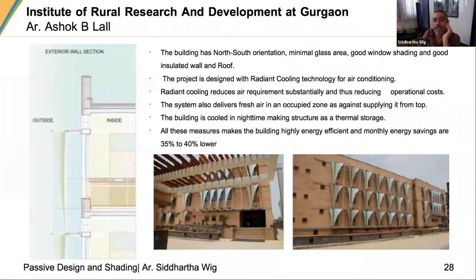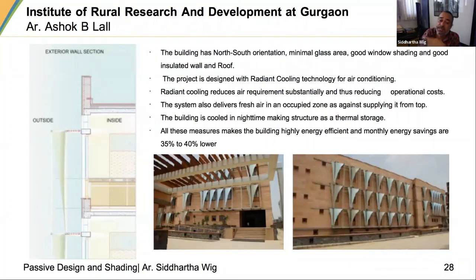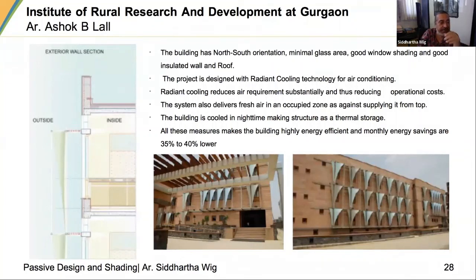The building uses its orientation well and windows are carefully designed. There is radiant cooling happening via radiant beams running through the building — far more effective than using large volumes of air, so it saves on air conditioning capital cost. They were able to achieve nearly 35 to 40 percent lower cost as well as higher energy efficiency for the air conditioning system. The shading devices are placed a little distance away from the building so that any heat gain on the devices is not transferred to the structure.